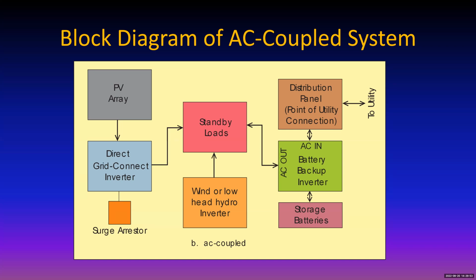There's no PV electricity, so the energy comes out of the storage batteries. If the batteries run too low and that inverter isn't able to start up again, it can't look like a utility to the direct grid connect inverter the next morning, and that inverter can't turn on, so you're out of luck. So there are interesting control functions to make sure there's always enough electricity left in the batteries to turn the direct grid connect inverter back on the next morning to capture more DC energy from the array.